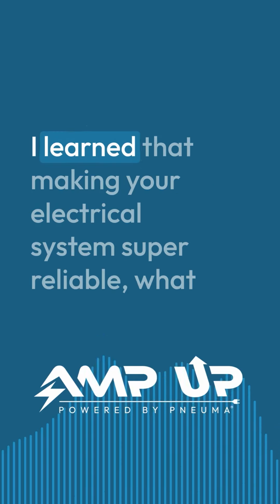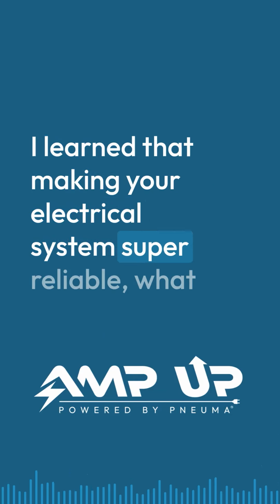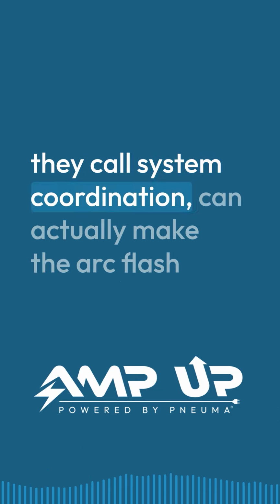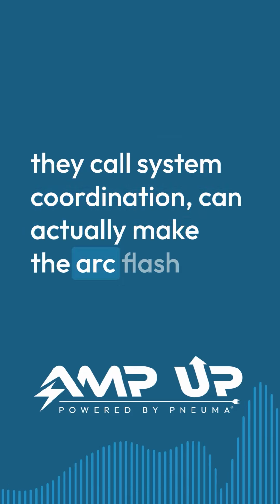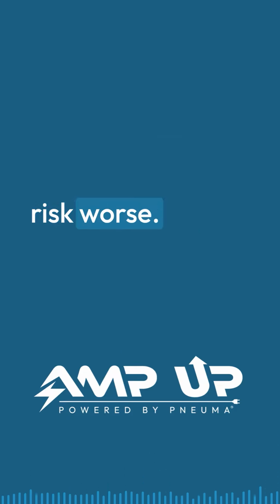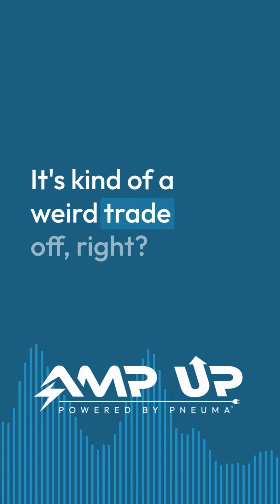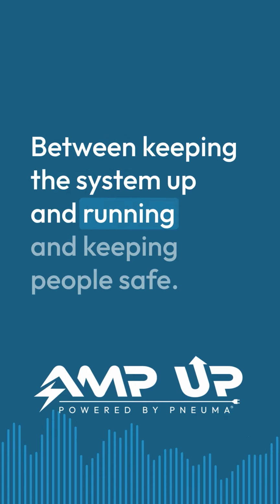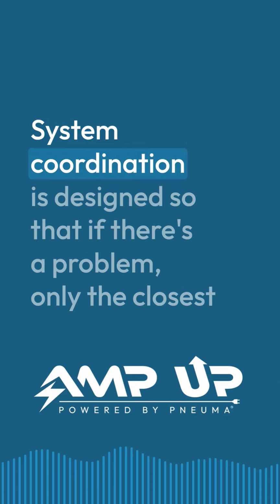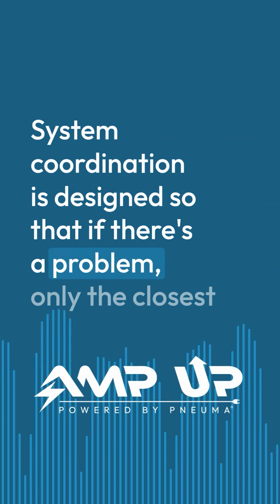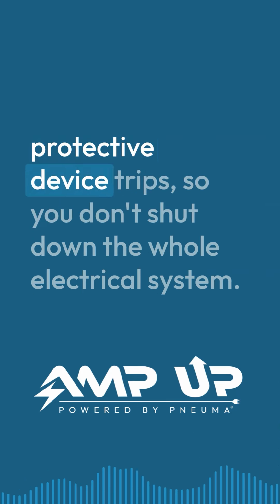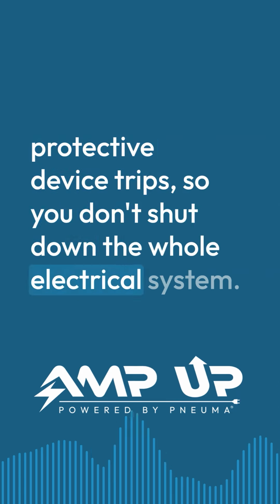You know, it's interesting. I learned that making your electrical system super reliable, what they call system coordination, can actually make the arc flash risk worse. How'd that work? It's kind of a weird trade-off, right? Between keeping the system up and running and keeping people safe, system coordination is designed so that if there's a problem, only the closest protective device trips, so you don't shut down the whole electrical system.